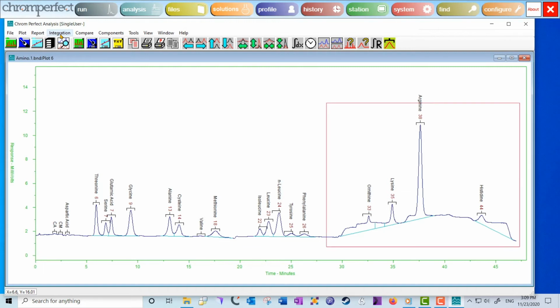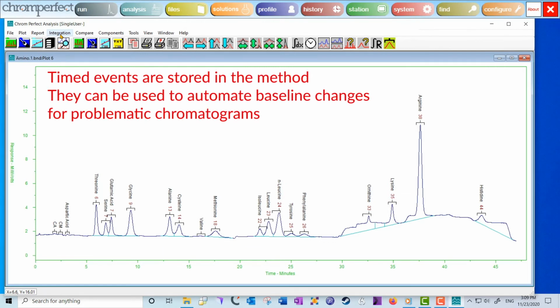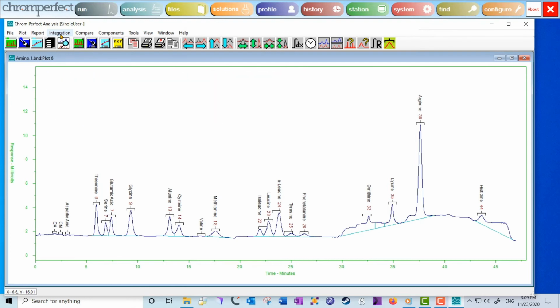Perhaps there is a disrupted baseline due to the switching of a valve. Perhaps the peak width increases with the retention time, so no single peak width setting is appropriate for all peaks. In a situation like this, Chromperfect needs additional hints to integrate the chromatogram properly. These hints are called timed events or integration events, and they are stored in the method file. Note, there are a great many of these events which are described in the main manual.